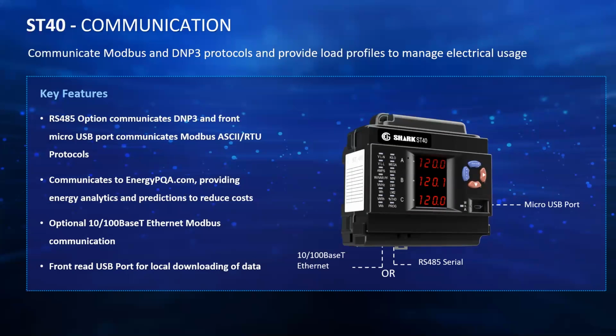This meter also has communication capabilities. We have a front USB port using micro USB. If you needed to get into the meter locally to retrieve logs, set up a profile, we can do that from the front panel. Also at the bottom of the meter, we have the option of a 10/100 Base-T Ethernet port or an RS-485 serial port. The Ethernet port will talk Modbus. If you choose to use the RS-485 serial port, we have Modbus RTU, Modbus ASCII, or DNP protocols for communication.